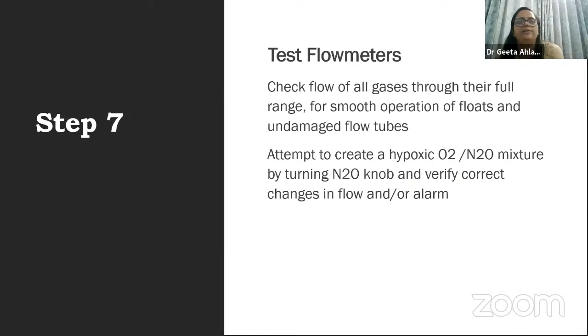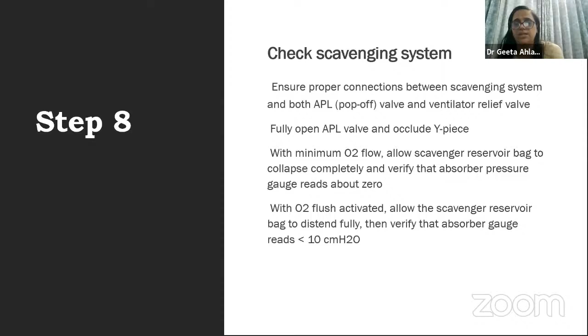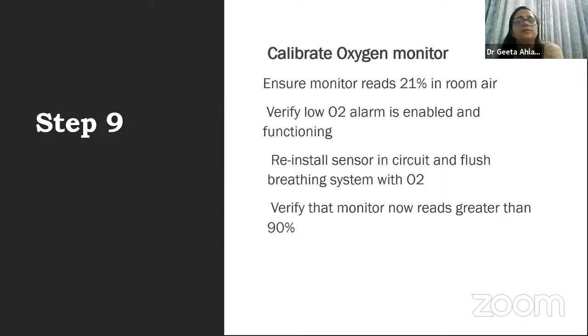Test your flow meters for all the knobs and all the things that we talked about. Check your scavenging system if you have one. Many institutes don't have this facility, but if you're in a position, check it thoroughly. Check your APL valve: occlude your Y piece and see that nothing comes out of it. Then release your APL valve and see whether there is a change. Calibrate all your oxygen monitors. It should show 21% on room air, and verify your low O2 alarm. Then you open the oxygen and immediately your reading should be more than 90.